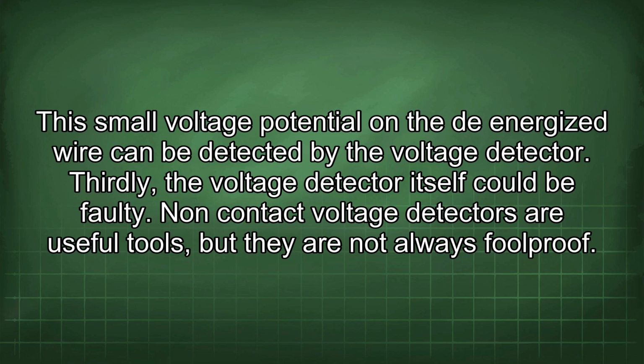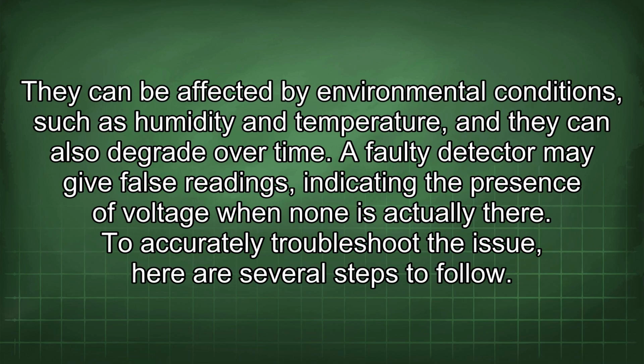Thirdly, the voltage detector itself could be faulty. Non-contact voltage detectors are useful tools, but they are not always foolproof. They can be affected by environmental conditions such as humidity and temperature, and they can also degrade over time. A faulty detector may give false readings, indicating the presence of voltage when none is actually there. To accurately troubleshoot the issue, here are several steps to follow.